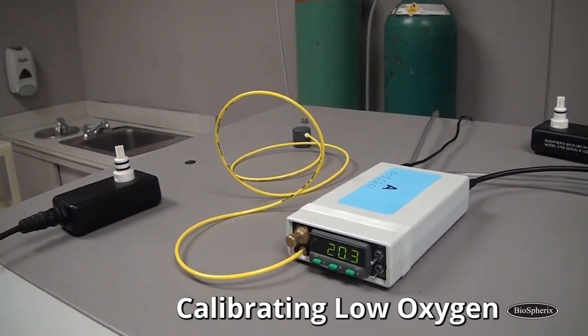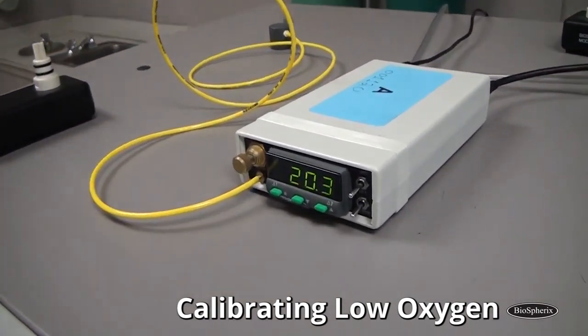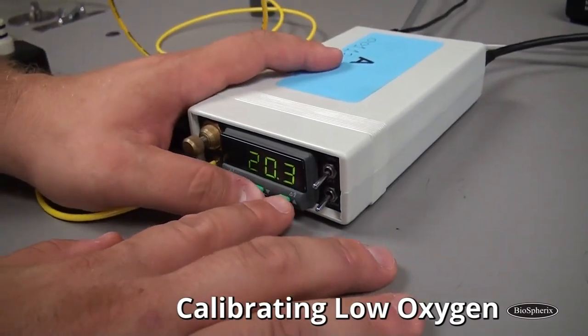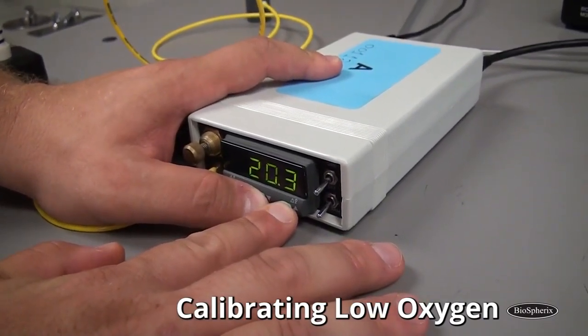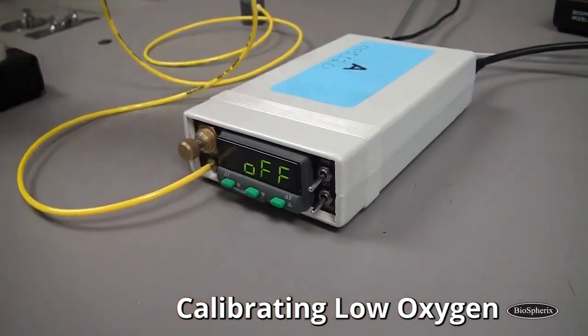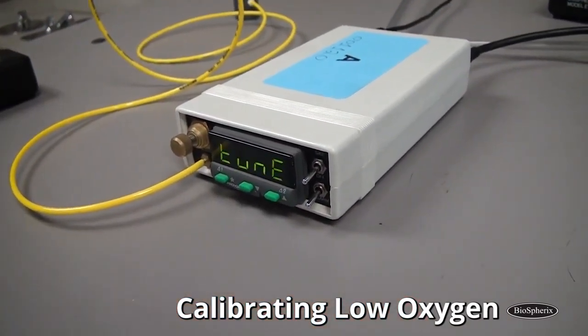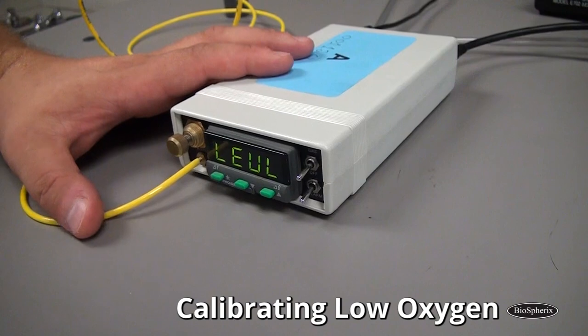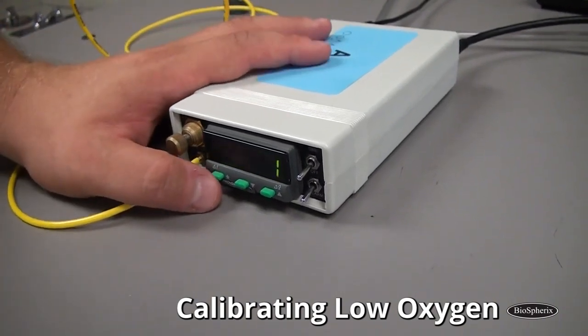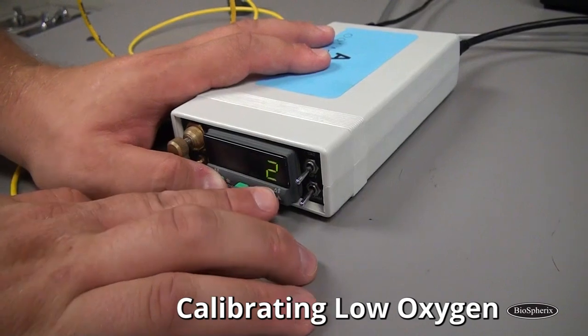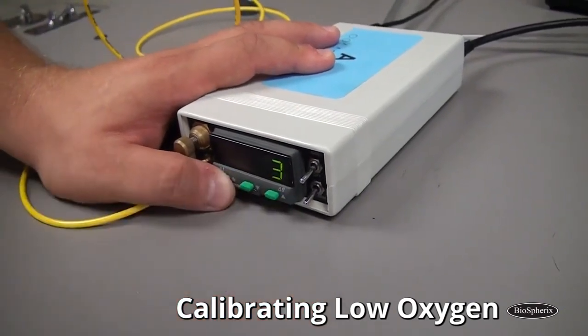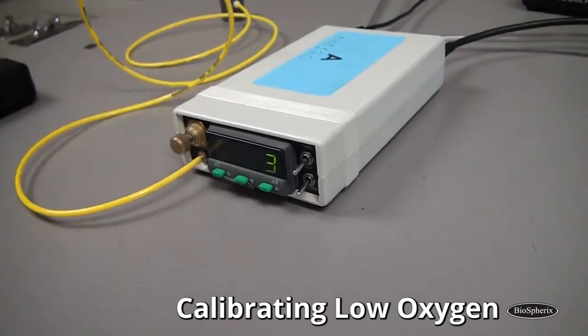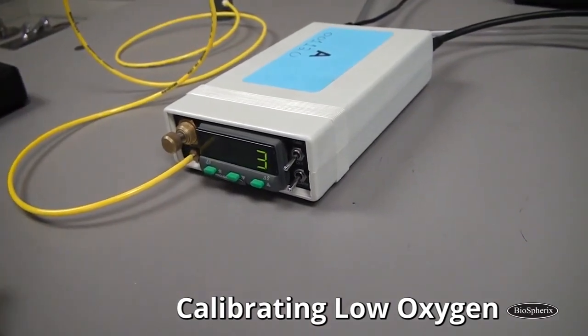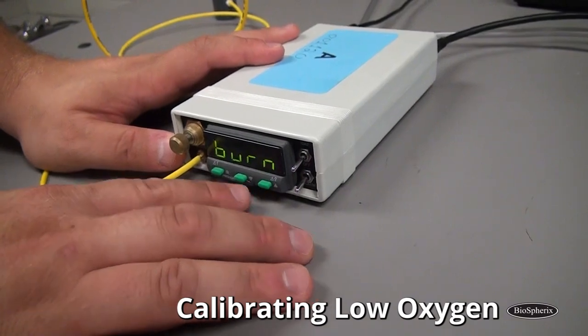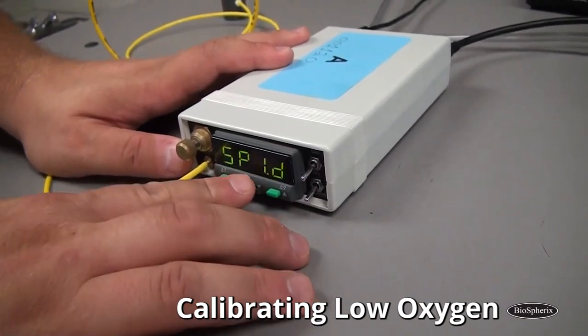So what I'm going to do is go into the program mode just like I did for the 0 calibration. Hold these for 3 seconds, the up and down. You'll see tune. You can let go because you're in the program mode. And if you press down, you'll go to the level function. Whenever you want to make a change to one of the functions, you just hold the star, and while you hold it, you press the up or down. And I've changed it to level 3. I'll let go of the star. And now I want to navigate through that level, and I can do that by pressing up or down. If you pass it by, you just hit down to go back to it.